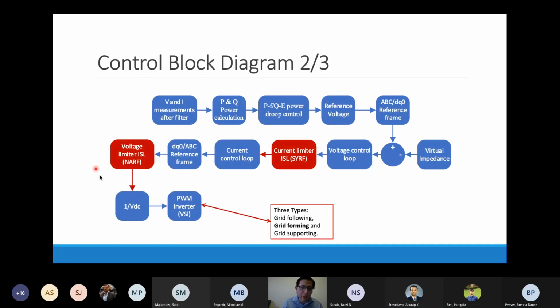This voltage reference we also pass to a voltage limiter for fault conditions in order to prevent over voltage or under voltage, to not further damage the inverter and, additionally, the equipment that is connected to it if we keep operating in this condition. From here, we connect into the pulse width modulation.